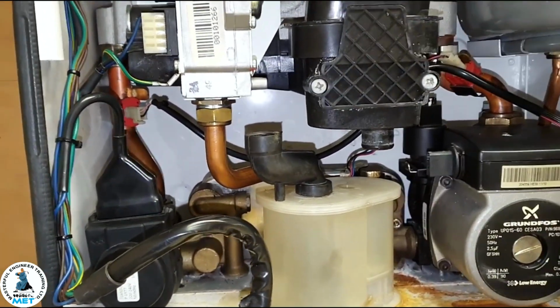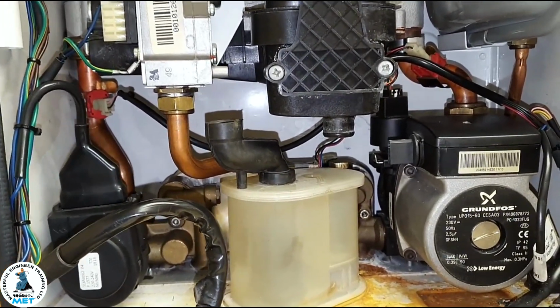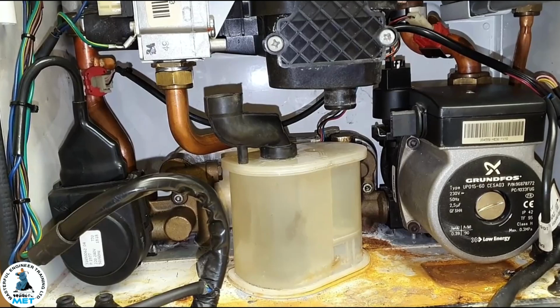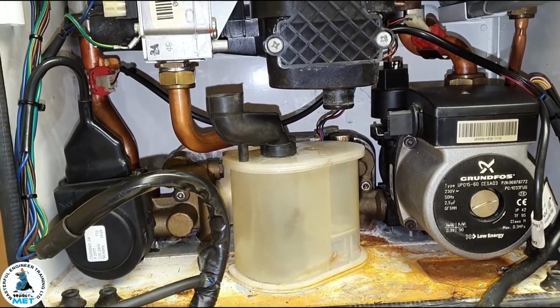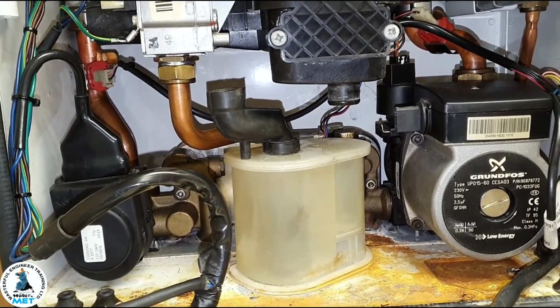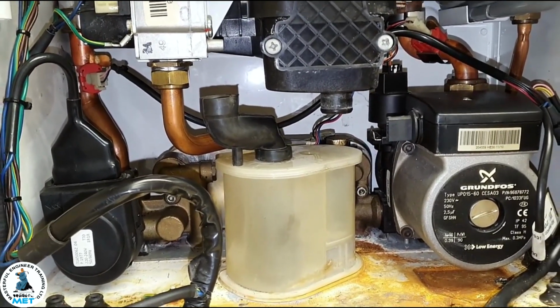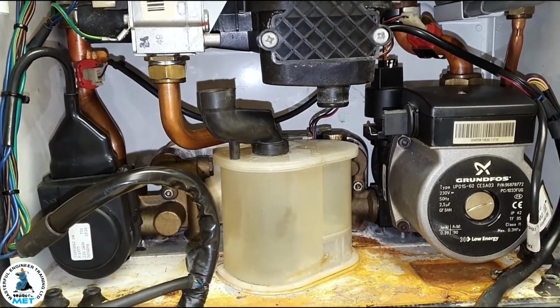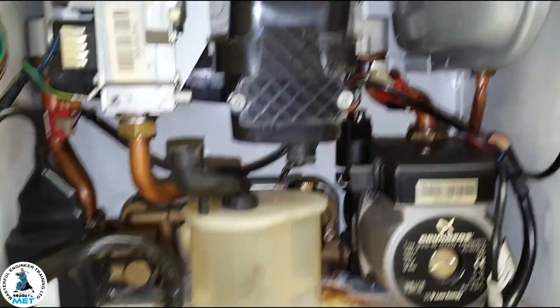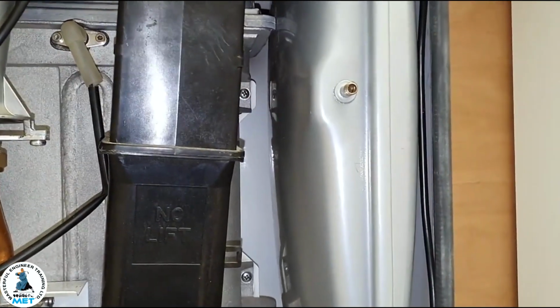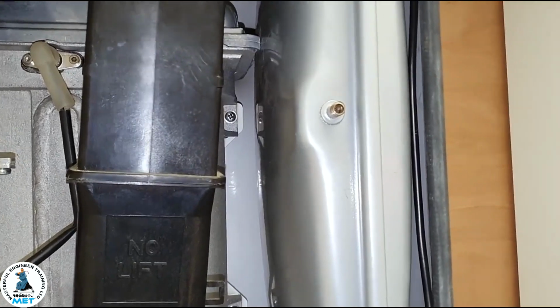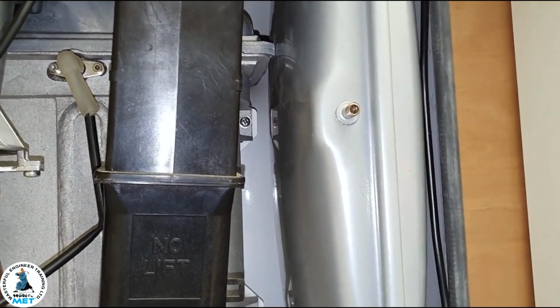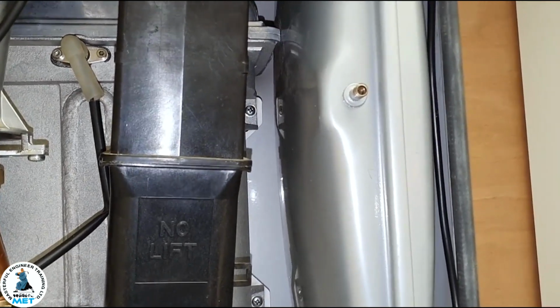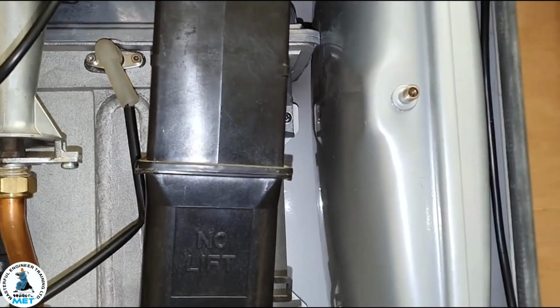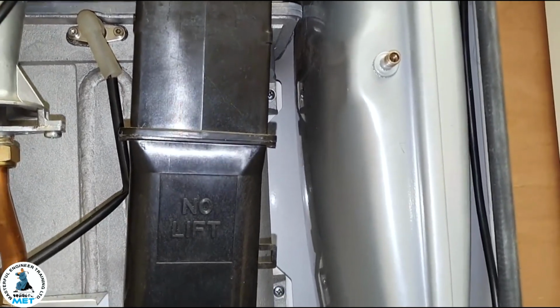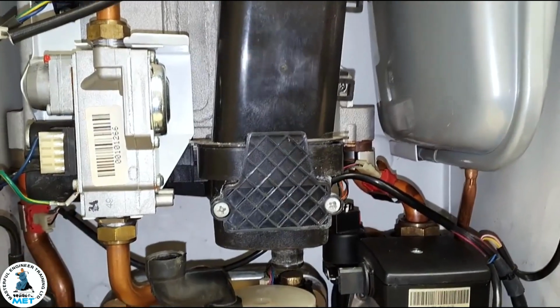So if a customer said to me, yeah, it happens every week or every 2 weeks, I top it up and then it runs, and then it comes back on, that means I've got a leak - it's definitely losing pressure through the system. So then I'll be looking at the expansion vessel, because it might be over-pressurizing as there's no air inside the vessel. So with that information from the customer, that's a red flag. Let's look at this, and hopefully that will solve the problem.